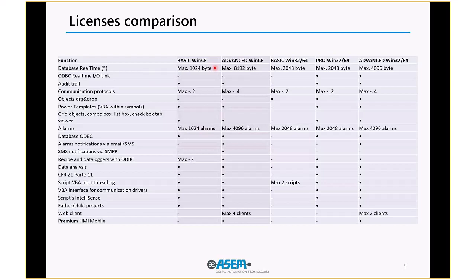You can build up a project with 10,000 tags. Even for Windows CE, there's absolutely no limitation in the number of variables you create in the project. The limitation is how many of them - we count this in how many bytes we read at a certain moment from the field, from the controllers, from the PLCs, one or many, connected to the HMI. So if you have a very big page with a lot of variables, a lot of alarms, a data logger, all those activities count from the point of view of maximum number of bytes.